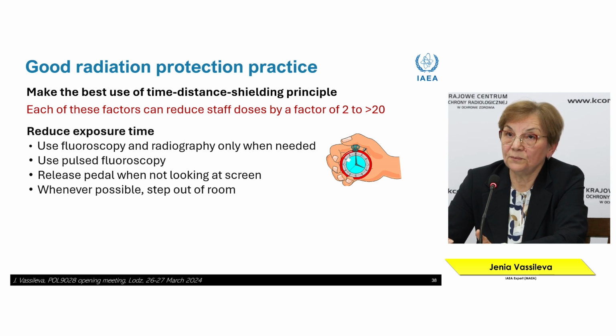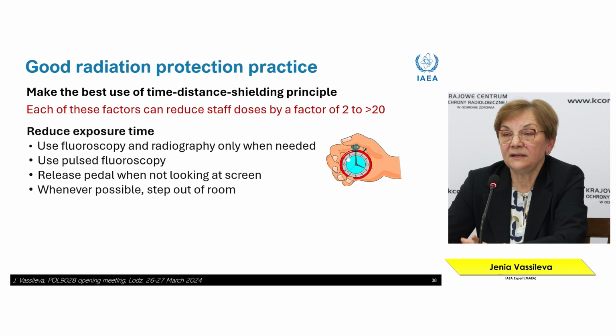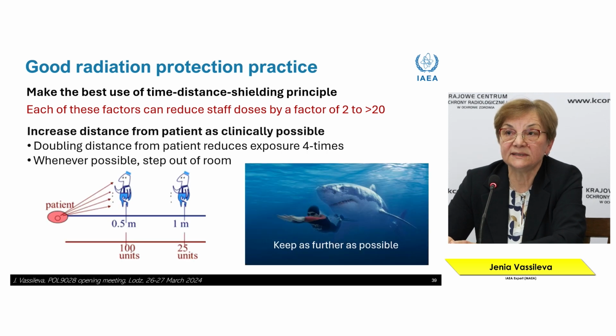Using pulse fluoroscopy helps reduce time, because pulses really reduce the time in which the X-ray generator is active. Whenever possible, step out of the room. Of course, it's not possible for the main operators, but it's possible for nurses, for example, who are there to assist and don't always need to be very close to the patient.